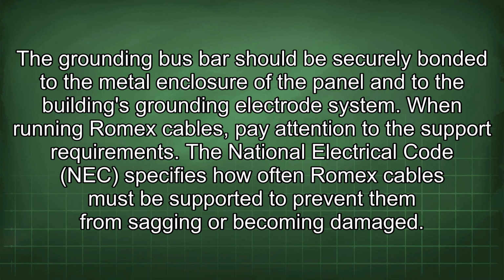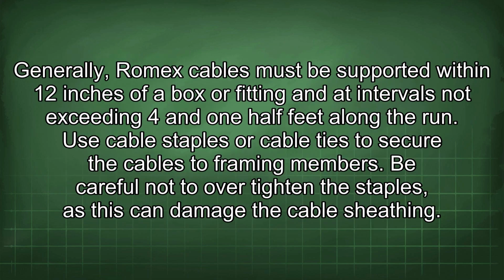The grounding bus bar should be securely bonded to the metal enclosure of the panel and to the building's grounding electrode system. When running Romex cables, pay attention to the support requirements. The National Electrical Code (NEC) specifies how often Romex cables must be supported to prevent them from sagging or becoming damaged. Generally, Romex cables must be supported within 12 inches of a box or fitting and at intervals not exceeding 4½ feet along the run. Use cable staples or cable ties to secure the cables to framing members. Be careful not to over-tighten the staples, as this can damage the cable sheathing.